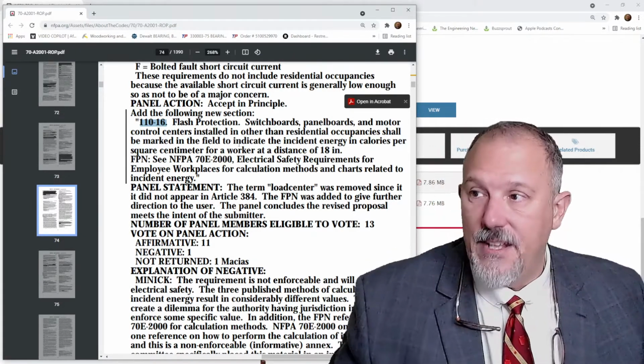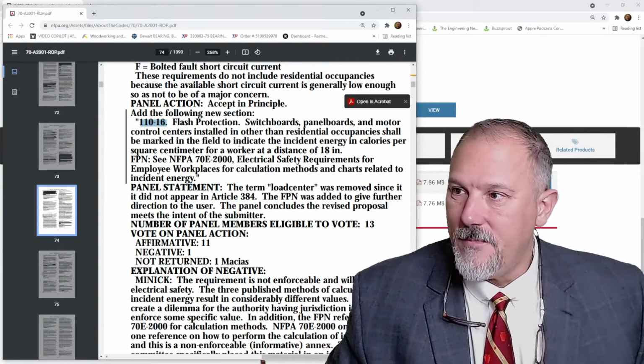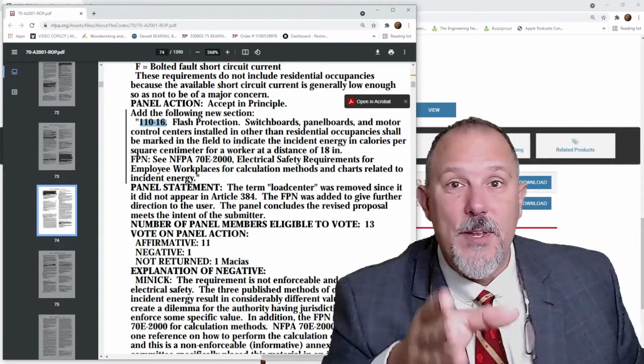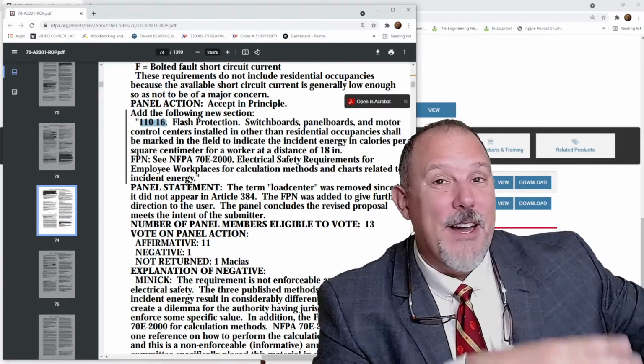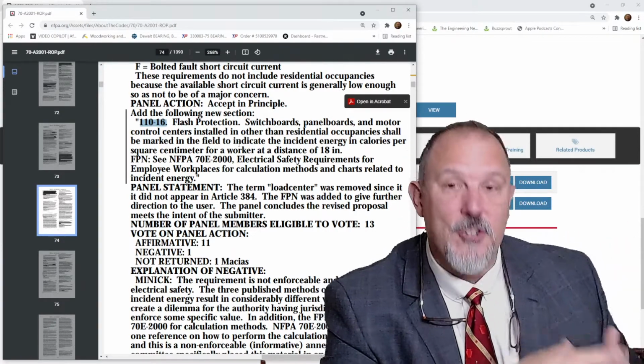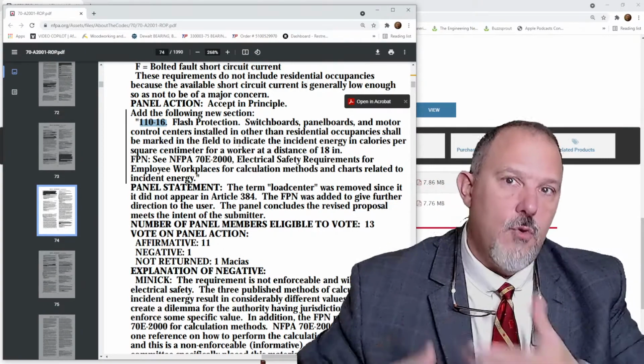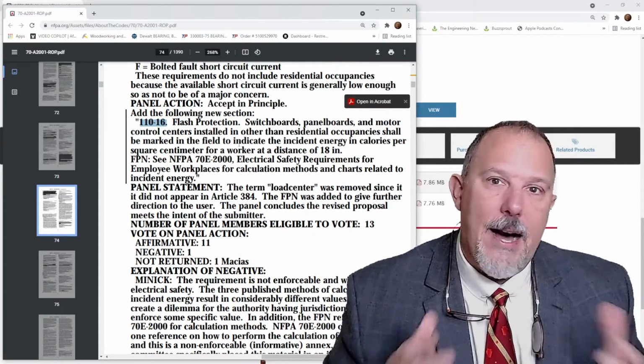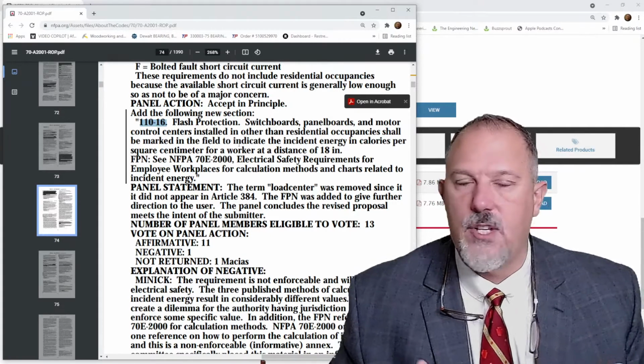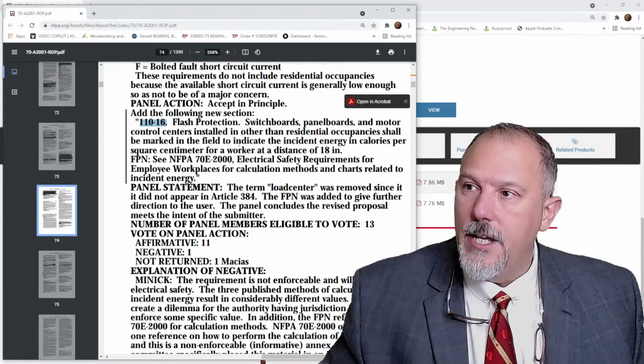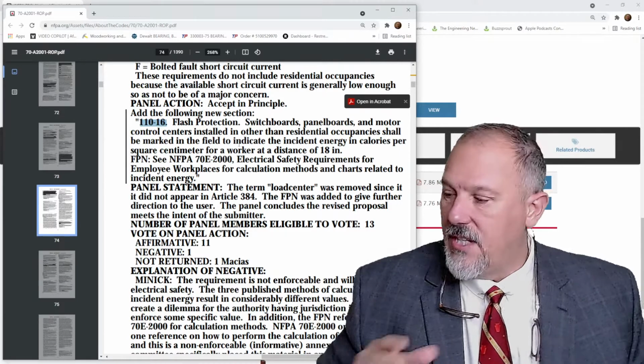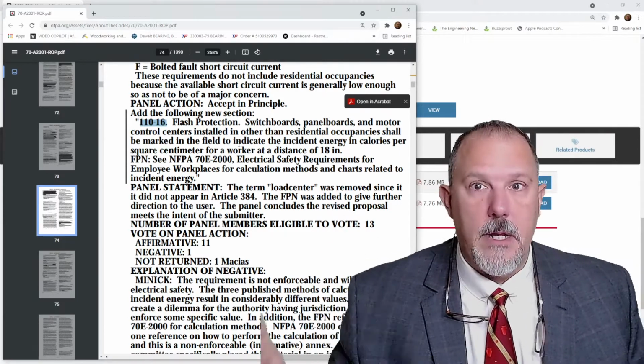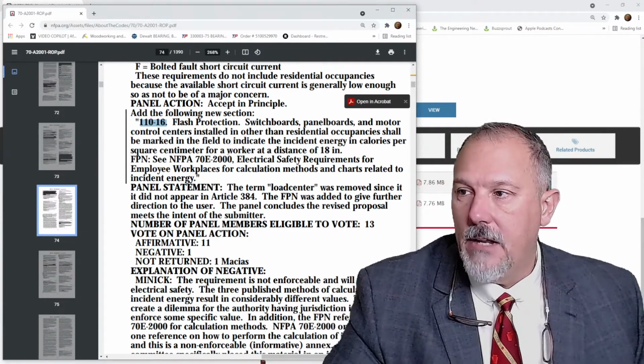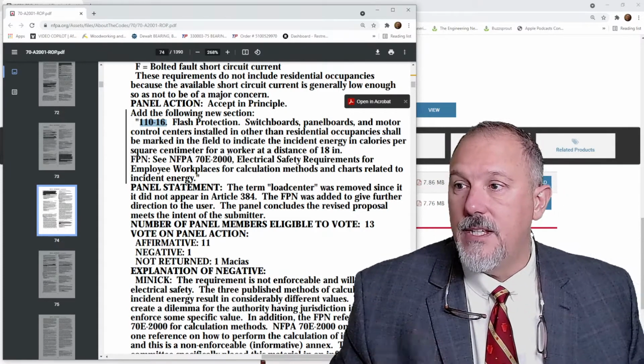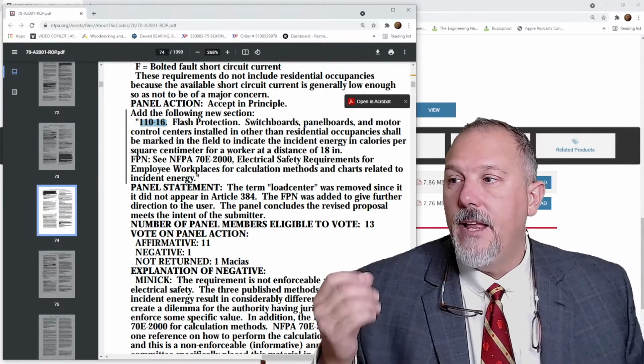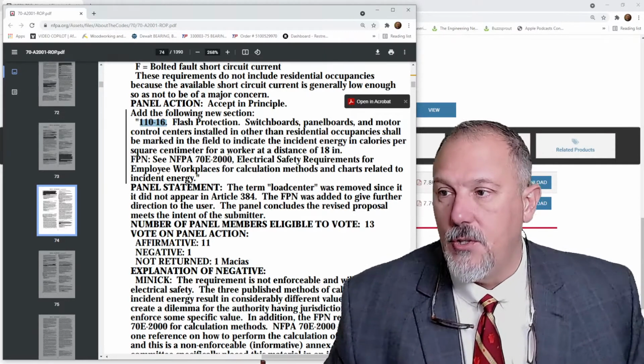And they referenced 70E 2000 for the methods, because here's what's going on. Think about it. You've got IEEE papers that are doing some research. They're coming up with equations. They're getting more and more of a handle on how to calculate these things called arcing currents and calories per centimeter squared. And they're being introduced into 70E, and they're putting the equations in there. And the panel statement was the term load center was removed since it did not appear in Article 384, and the fine print note was added to give further direction to the user.